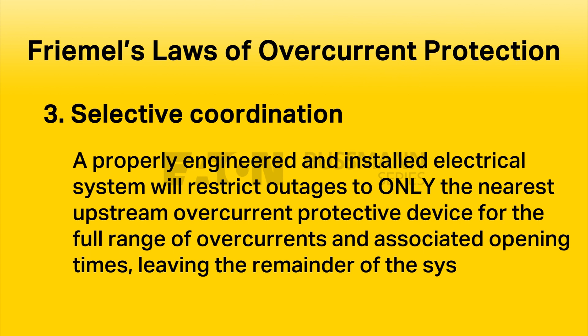Finally, Friemel's third law of overcurrent protection states that a properly engineered and installed electrical system will restrict outages to only the nearest upstream overcurrent protective device for the full range of overcurrents and associated opening times, leaving the remainder of the system undisturbed and preserving system continuity. Numerous NEC sections now require selective coordination for critical systems, such as elevators, emergency systems, legally required standby systems, critical operations power systems, and more. Reliability and safety are paramount in these systems and are a key factor in selecting the overcurrent protective device.